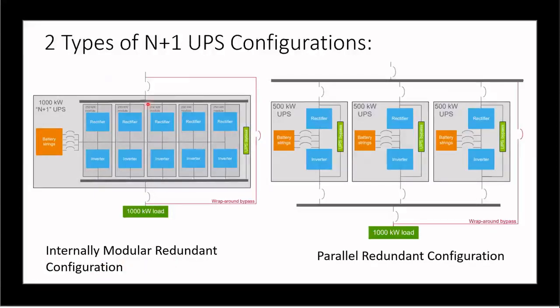This is helpful because many times if maintenance is required or if something goes wrong, we have an extra module that is supporting the load. This is the parallel redundant. So there will be 3 different UPSs. Here there is only one UPS with different power modules, while here it will be 3 different UPSs. So if something goes wrong with one UPS, then the other UPSs will be supplying the load. So there is a difference, right? Why they have created these 2 types, we will see here.